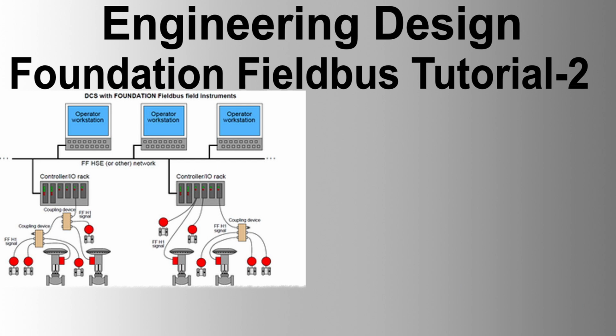Block mode, mode BLK. All blocks have their mode, expressed by this parameter. It is a record of 4 components: target, actual, permitted, and normal. The mode can be one of OS, man, auto, CAS, RCAS, and ROut.